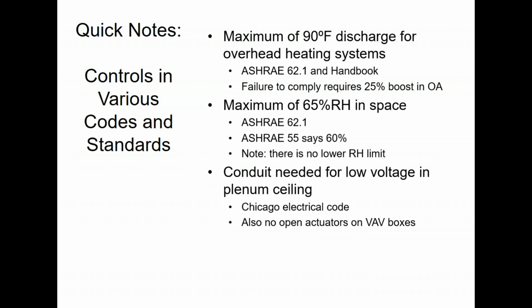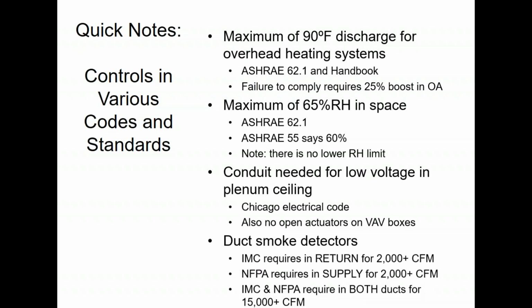For you controls guys doing City of Chicago work, whenever you have a plenum ceiling, they're going to make you put everything in conduit. You probably already know that, but it doesn't matter if it's 1 volt DC wire, they still want it in conduit. Ethernet cable, conduit, right? 24 volt AC wire, conduit. Everything goes in conduit in the city of Chicago. It's the only place I know of in the country that makes you put all the low voltage wiring in the plenum in conduit. You also cannot have open actuators because they have control wiring on them. On the shaft, you have to put them in a control enclosure as well on the VAV boxes.